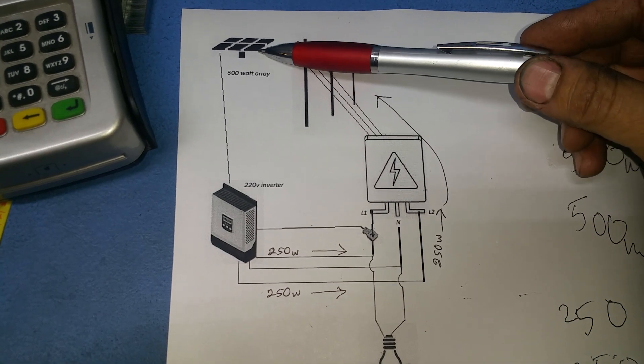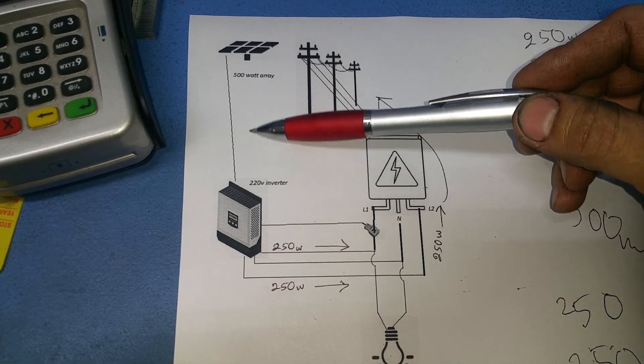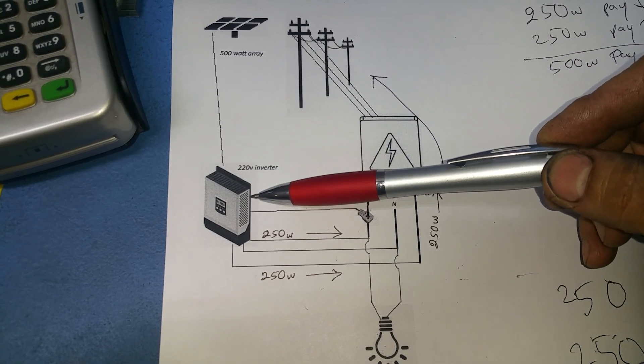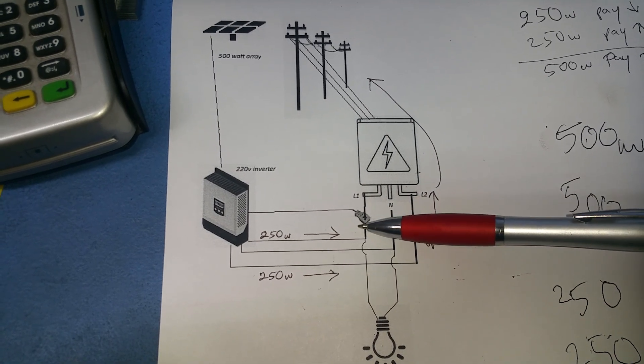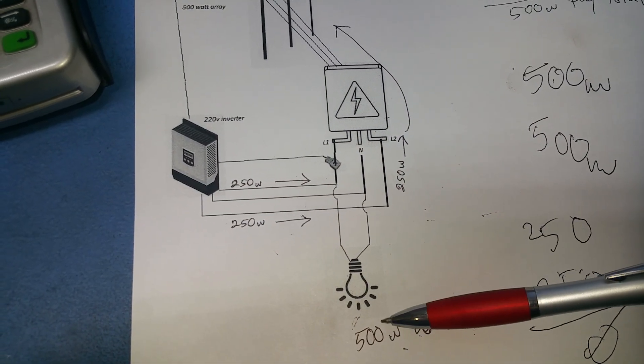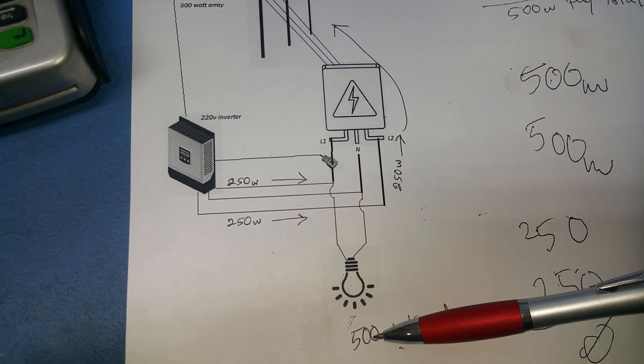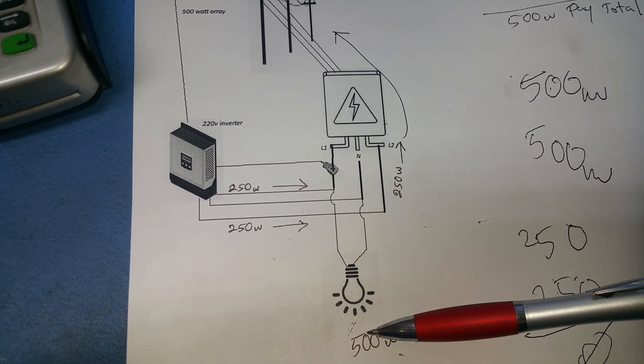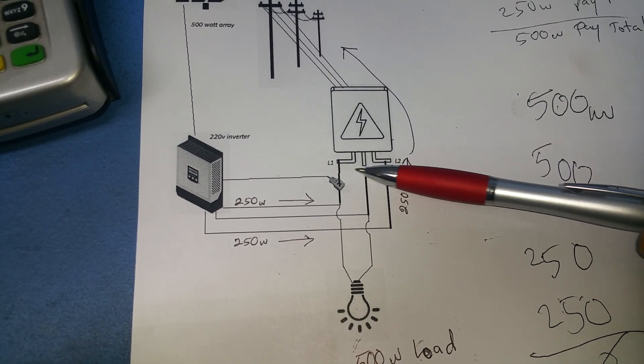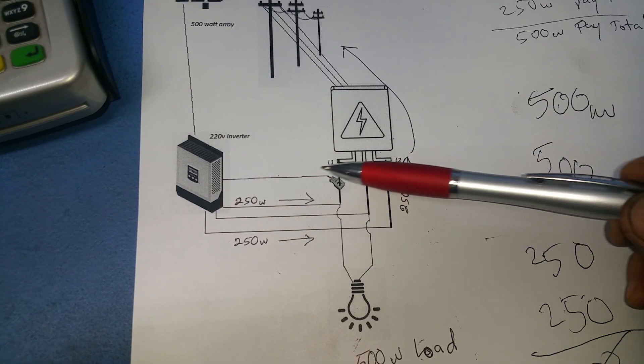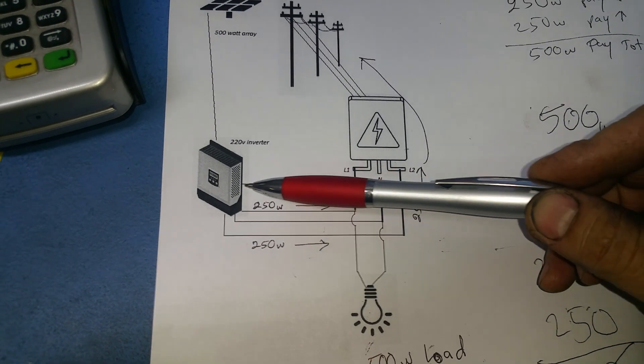I turn on the load and the array puts out 500 watts into the inverter. The inverter has a sensor that sees the load is on, there's 500 watts. This load happens to be 120 volts which is on one of the phases only, in this case L1. The inverter sees that I'm taking out 500 watts, so it will put out 500 watts to accommodate for that.